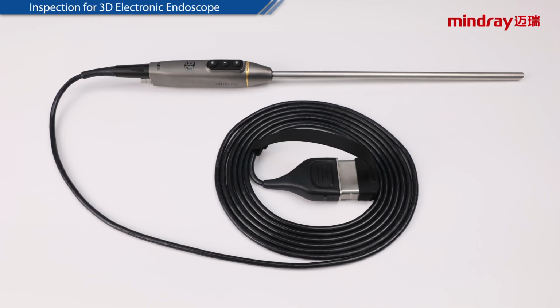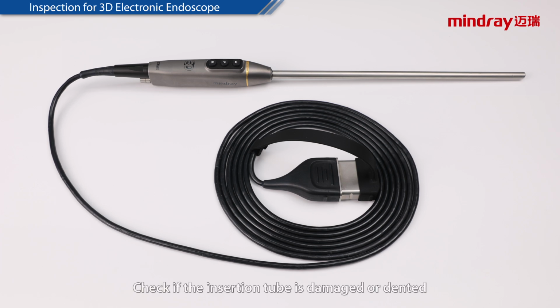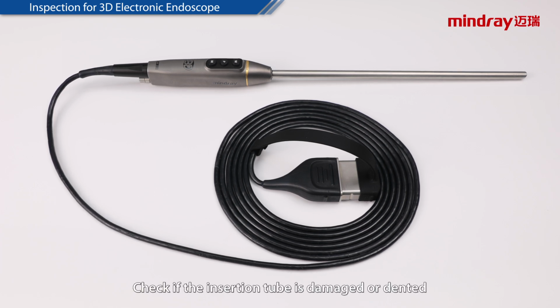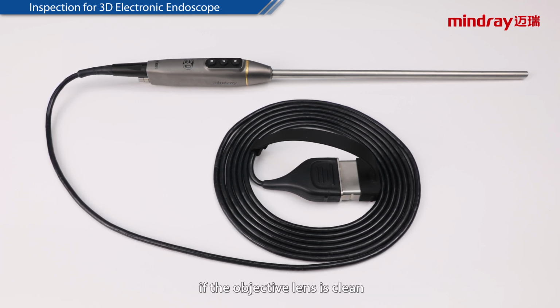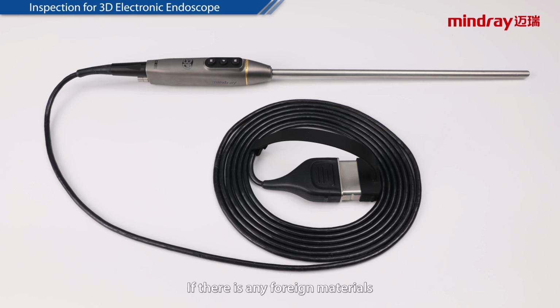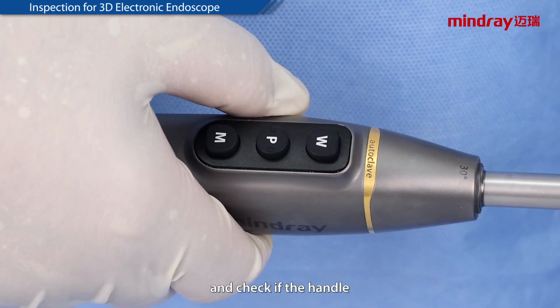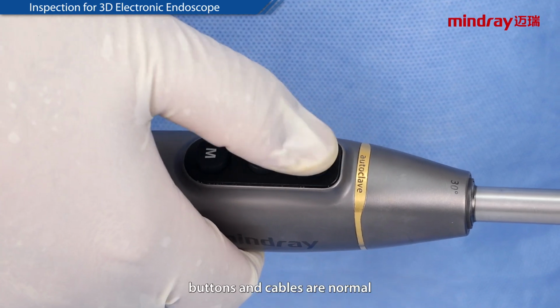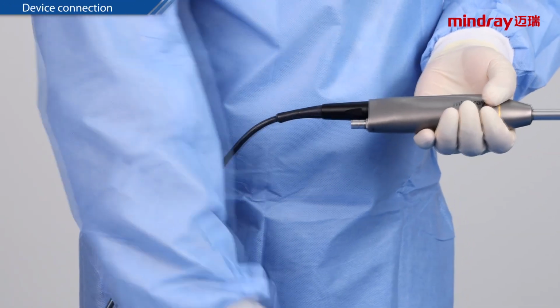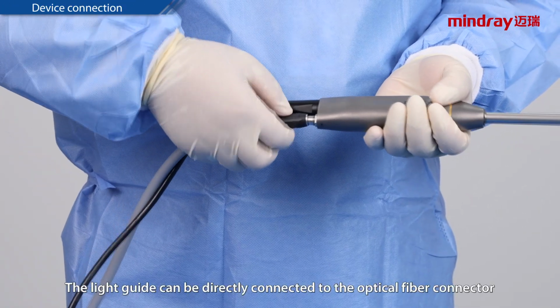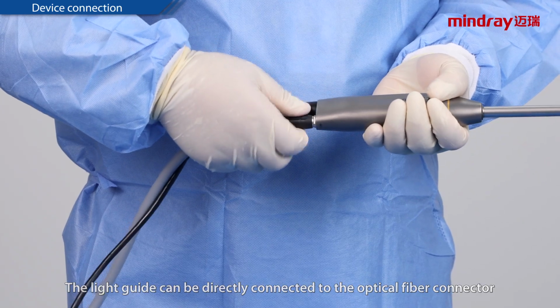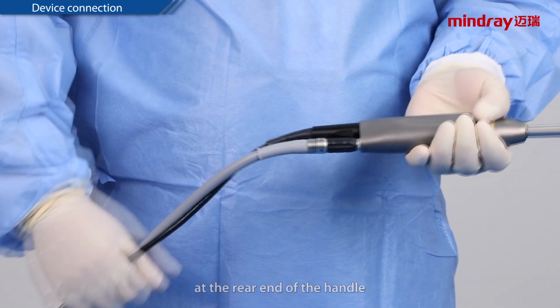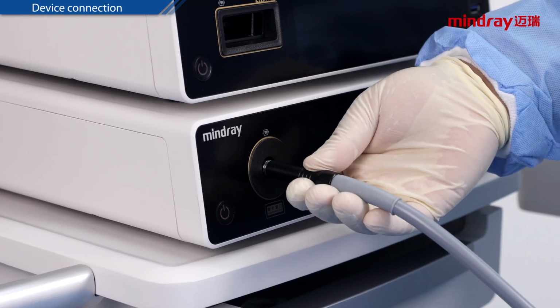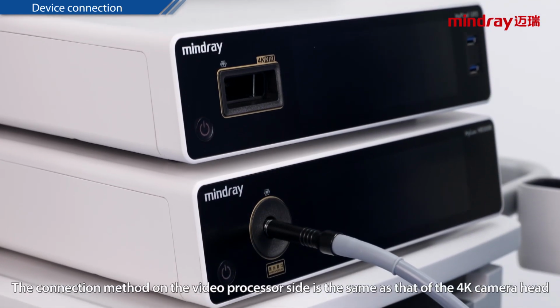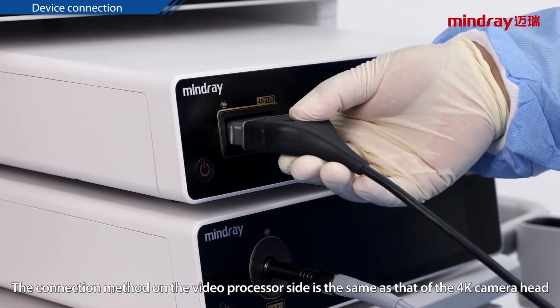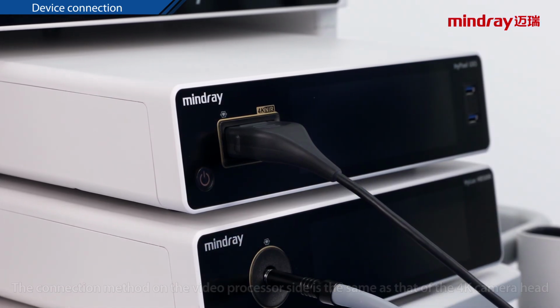Inspection for 3D electronic endoscope. Check if the insertion tube is damaged or dented, if the objective lens is clean, if there is any foreign materials. Wipe it with sterile gauze and check if the handle, buttons, and cables are normal. Device connection. The light guide can be directly connected to the optical fiber connector at the rear end of the handle. The connection method on the video processor side is the same as that of the 4K camera head.